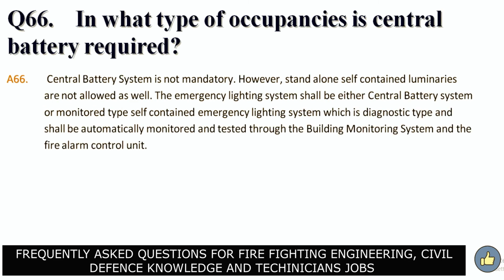In what type of occupancies is central battery required? Answer. Central battery system is not mandatory. However, standalone self-contained luminaires are not allowed as well. The emergency lighting system shall be either a central battery system or a monitor type self-contained emergency lighting system, which is diagnostic type and shall be automatically monitored and tested through the building monitor system and the fire alarm control unit.